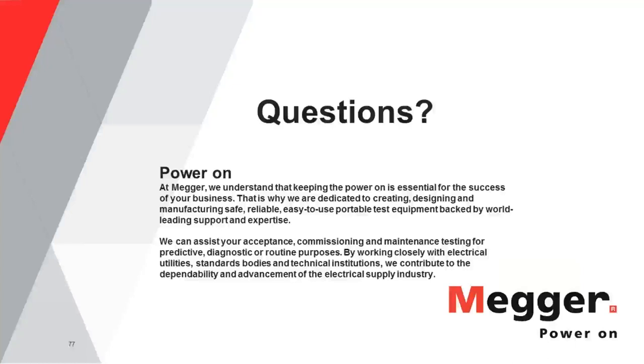Okay, so when testing cables, what you need to consider is that cables will represent a very high capacitance, so they can store a lot of energy, and you might not be able to charge that capacitance to determine if your insulation is good or bad. And that's when you need to use another type of equipment for cable testing, and that's why these other tests, such as tan delta or very low frequency tests on cables, have been developed for diagnostics. Also for fault location, you need a lot of energy to be able to create a fault that you can locate when you are trying to find the place of that fault.